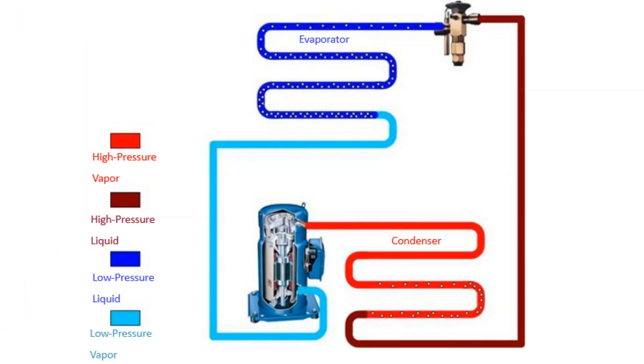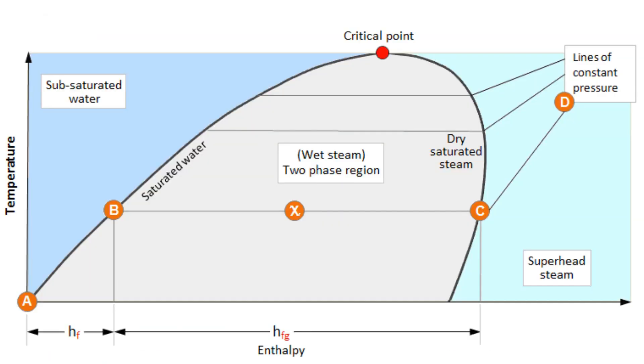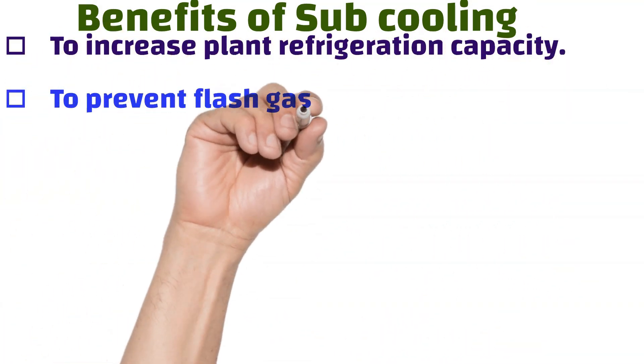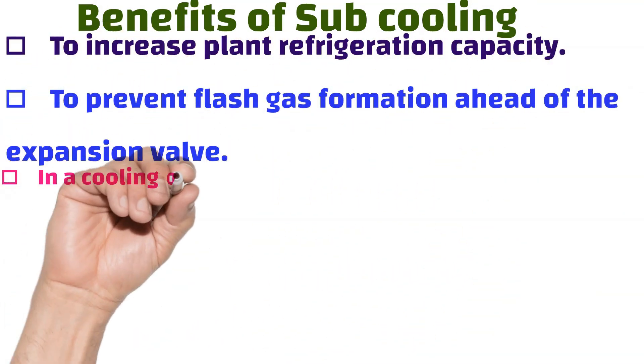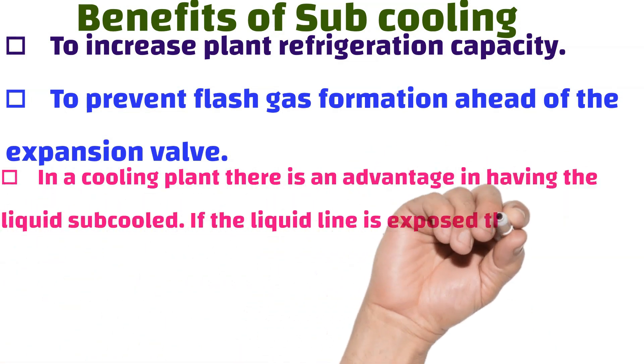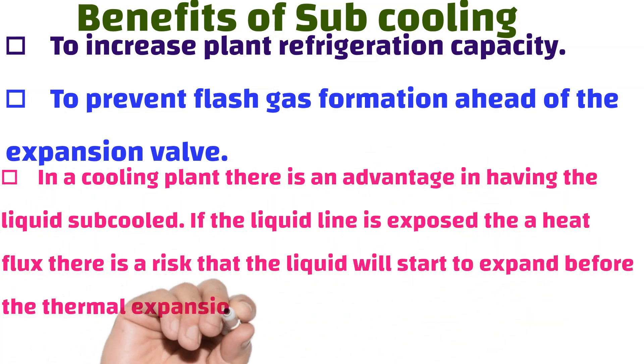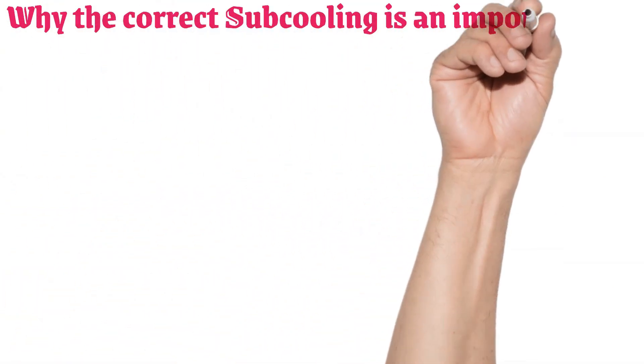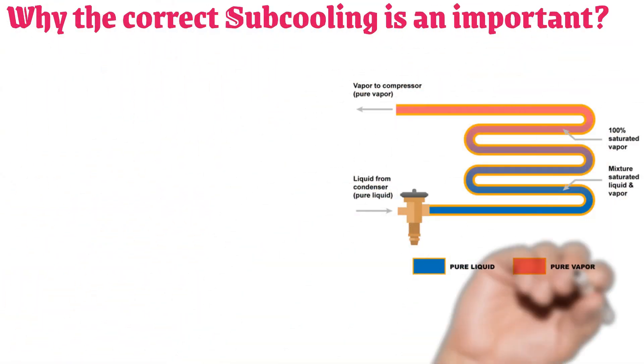Benefits of sub-cooling: one, to increase plant refrigeration capacity; two, to prevent flash gas formation ahead of the expansion valve; three, in a cooling plant, there is an advantage in having the liquid sub-cooled — if the liquid line is exposed to heat flux, there is a risk that the liquid will start to expand before the thermal expansion valve, causing flash gas, and the evaporator will fail to work.